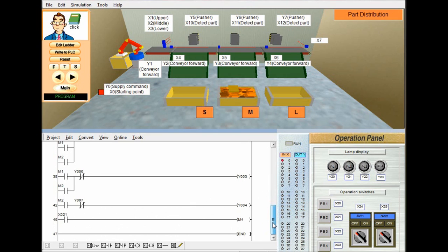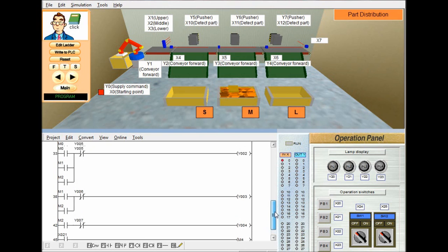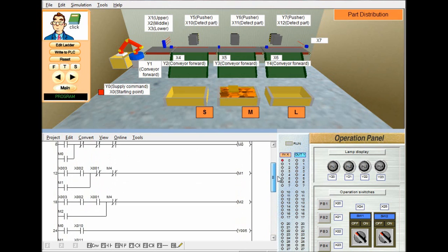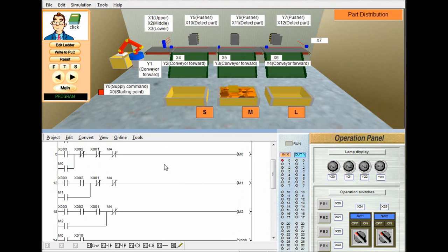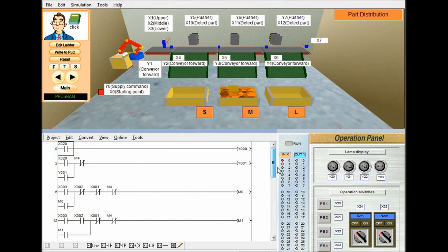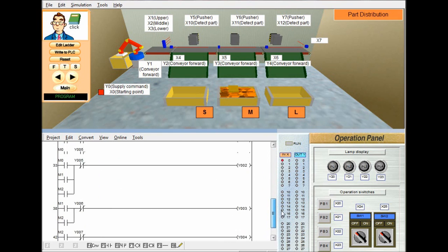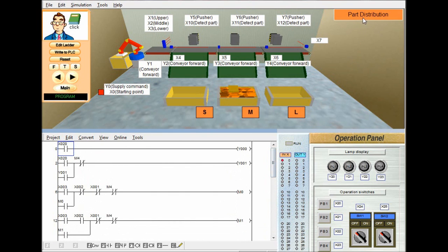Finally, there is one more input contact X21 — a push button contact. Whenever we press PB2, it will energize M4. M4 is used for the reset/erase function. M2, M1, M0 are connected along with the M4 contact and will get delatched. Also Y1, the first conveyor latch drive, also gets delatched. So this is the complete program we have written for part distribution.